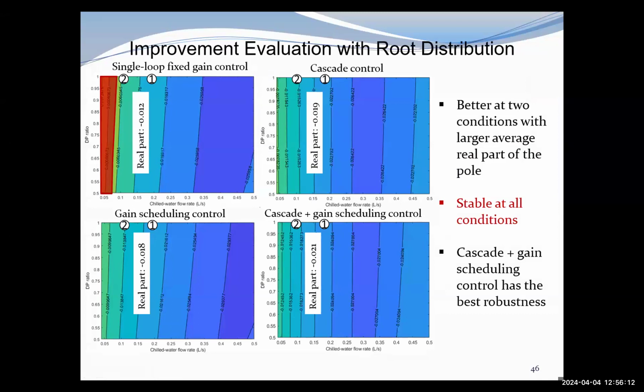Similarly, we simulate the control performance under all operation conditions with the variable chilled water flow rate and the DP. Here, the upper left figure shows the root distribution with a single loop fixed gain control. We can see here we have a positive real part, which means an unstable region. And by using the other three advanced control strategies, we can see the system root locations are all negative. That means the system's stability can be guaranteed by using any of the control strategies. And the cascade plus gain scheduling control can have the best robustness.